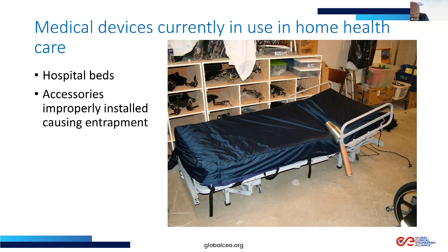Unfortunately, when one of the cylinders next to a side rail deflates, it creates a gap that allows a patient to slide between it and their neck can get caught in the side rail. And this test device, again, illustrates the size of the gap that can be created when that particular component of the mattress is in a deflation mode. Again, the patient was caught between the mattress and the side rail, and they suffocated and died.